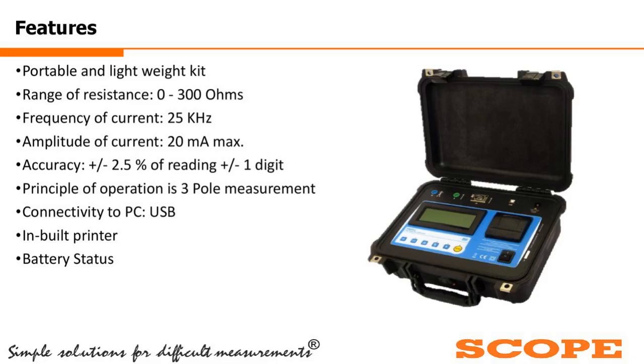There are some manufacturers in the market who offer an earth resistance meter with an accuracy of 0.5% and sell it at a bomb. Some people have asked me, no, I require this. Don't ask me why, I want to measure it accurately. That could be a separate 2 hour discussion on how they are showing that 0.5%, what the limitations are, and how in the Indian continent it is actually giving 2% accuracy. That could be a separate day, separate discussion, if that scenario comes.